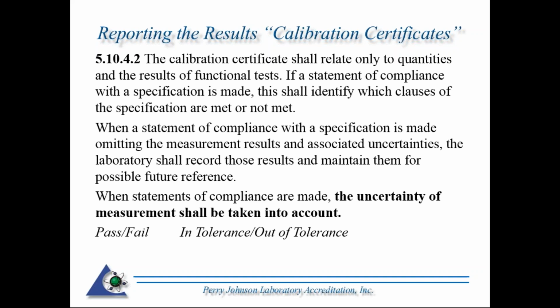When a statement of compliance with the specification is made, omitting the results and the associated uncertainty, the laboratory shall record these results and maintain them for possible future reference. Again, we already specified that you have to have those records available and should be able to recalculate the uncertainty and have all the records that are needed to do that. Again, when statements of compliance are made, the uncertainty of the measurements shall be taken into account.